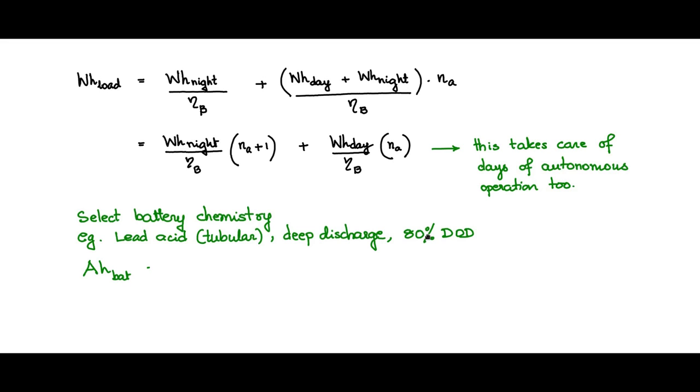The ampere-hour of the battery can be calculated as watt-hour load. This watt-hour load is as calculated here, which includes the efficiency of the battery also, divided by DOD times V battery nominal.